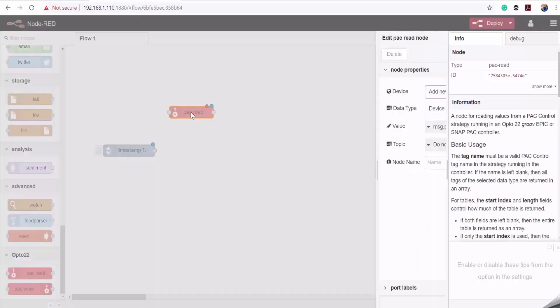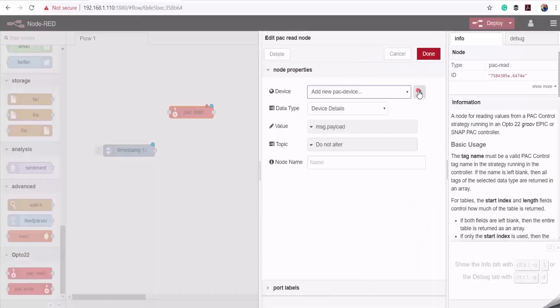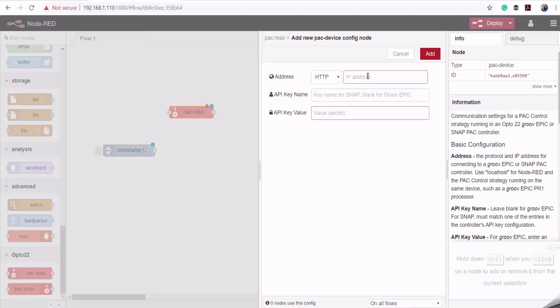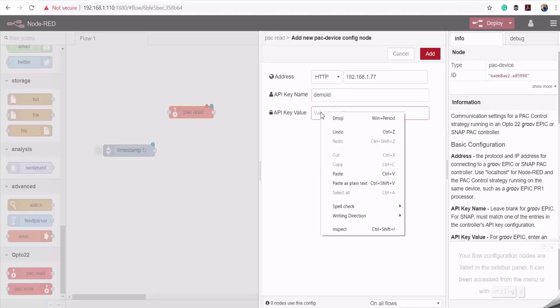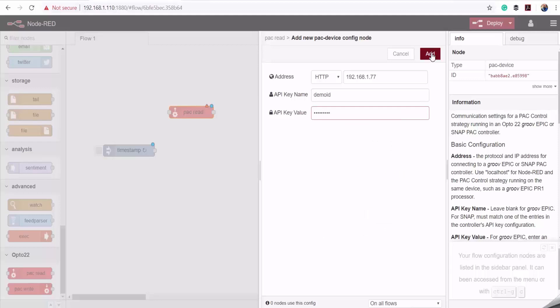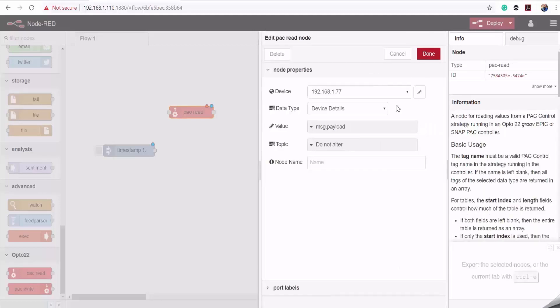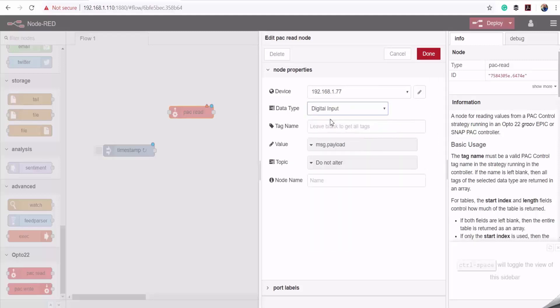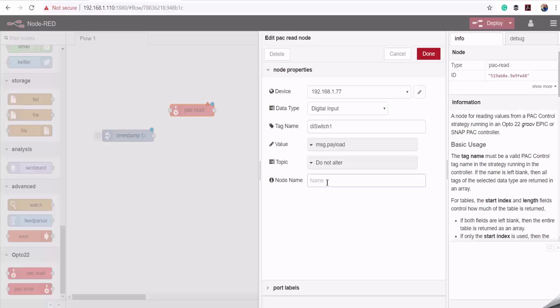I'll double-click on it to edit its properties and select 'Add new PAC device.' I'll enter the IP address of my industrial controller, then enter the API key name which has been pre-configured on the controller, and enter the value. I'll click Add. I need to select the type of input I want to read, which is digital input, and then enter the actual tag name as described on the controller, followed by the display name for this node.